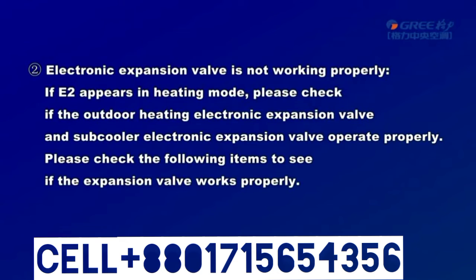2. Electronic expansion valve is not working properly. If E2 appears in heating mode, please check if the outdoor heating electronic expansion valve and subcooler electronic expansion valve operate properly. Please check the following items to see if the expansion valve works properly.